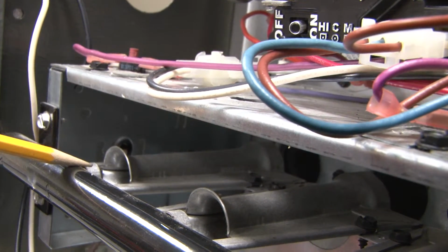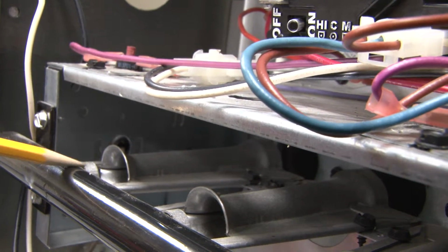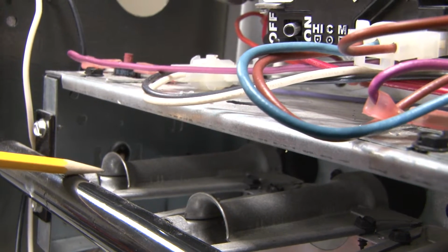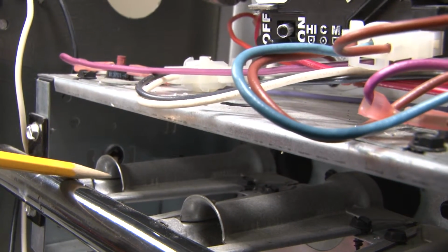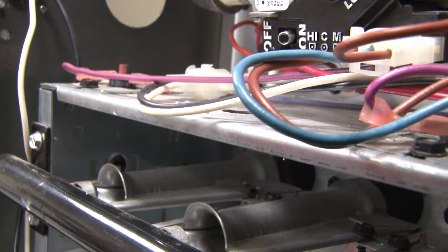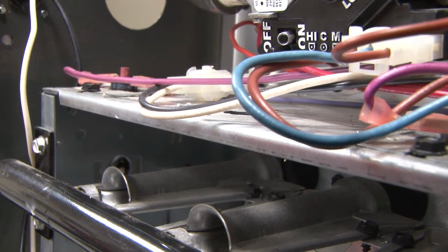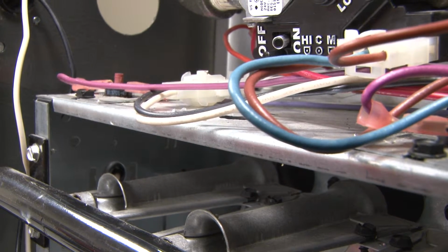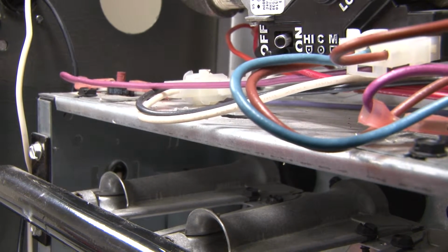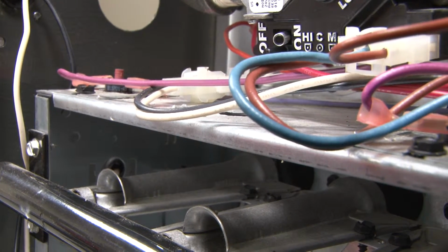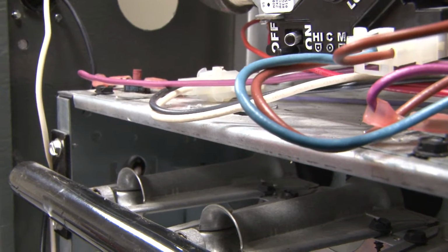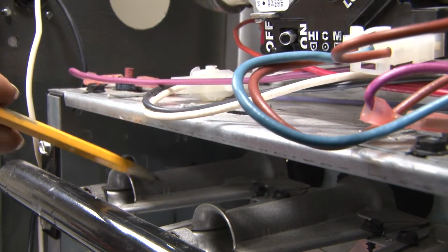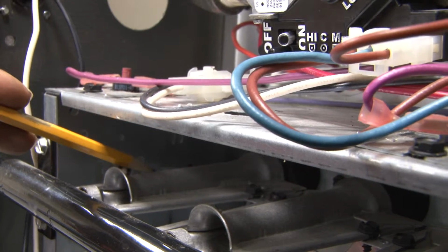So this, at the nozzle, is a small opening in the orifice that under pressure will shoot a stream in, and it will help drag the air around it, which is stagnant, to move along with it and cause it to mix with the fuel at the right proper velocity and combination of air and fuel.